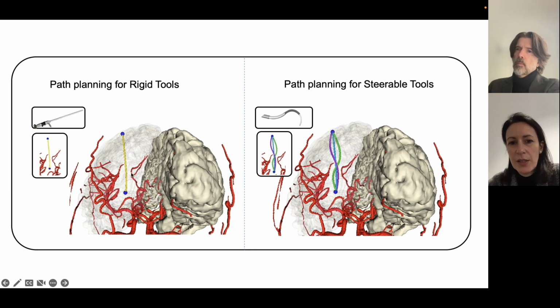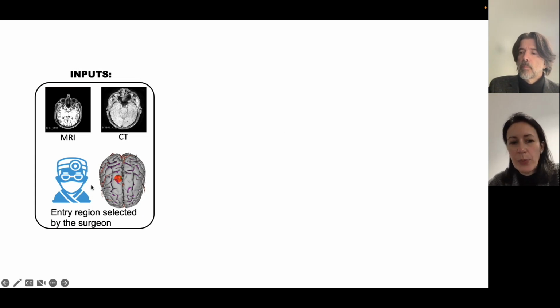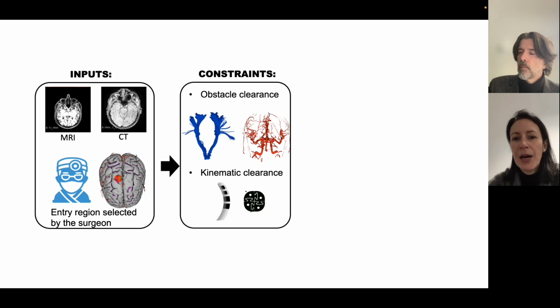A steerable catheter, with respect to a standard rigid probe, offers the possibility of numerous trajectories instead of the single trajectory, starting from, for example, the single entry point. The catheter that we used was able to perform, as I said, curvilinear trajectories inside the brain, and the aim is to get to the target, avoiding all the obstacles around, which are represented by the vessel tree. In general, in our setup, what are the inputs? The inputs are the preoperative images through which we can set the target and the obstacles, which are the regions that we need to avoid. The path that we have to undertake has some constraints, which are represented by the obstacles and the kinematic possibilities of our catheter. In our case, we had a minimum radius of curvature that we had to respect because of the kinematic constraint of the catheter.